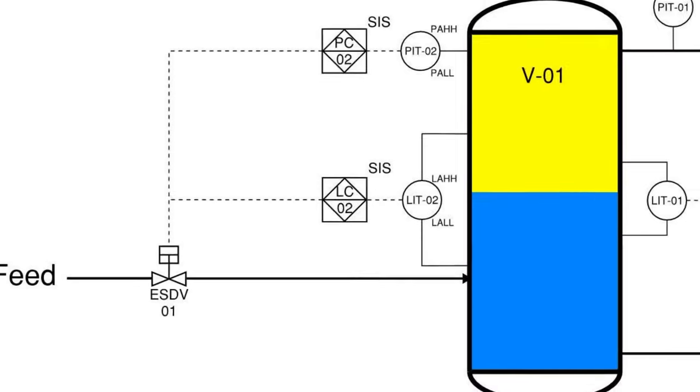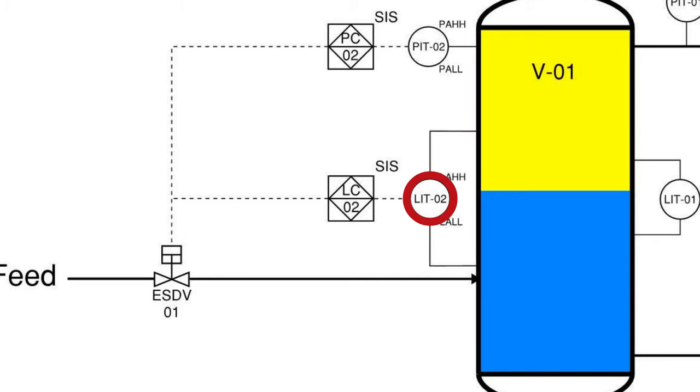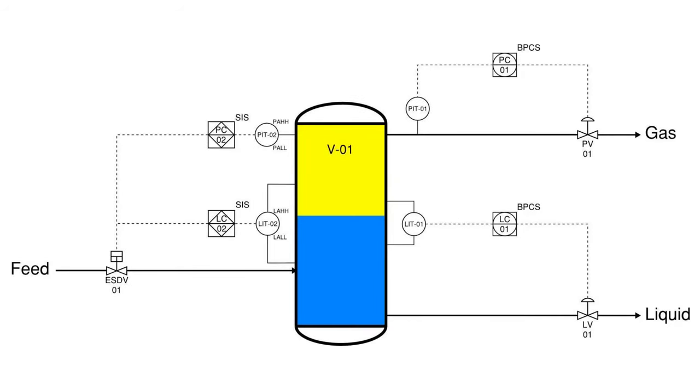Looking back at the vessel, the level transmitter LIT-2 is sensing liquid level in the vessel and transmitting a signal to the level controller LC-2, the level controlling function on the SIS. During normal operations, the BPCS will be controlling the level and there is no need for the SIS to act.